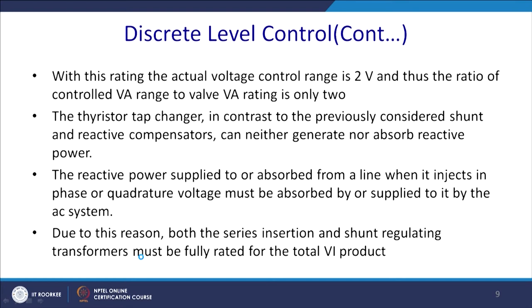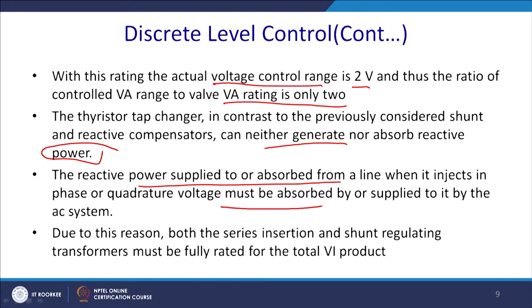With this rating, the voltage control range is 2V, and thus the ratio of the control VA range to the valve VA rating is only 2. The thyristor tap changer, in contrast to the previously considered shunt reactive compensator, can neither generate nor absorb reactive power. Okay, so they cannot control the real power. The reactive power supplied or absorbed from the line when it injects in-phase or quadrature voltage must be absorbed or supplied by the AC system or load.